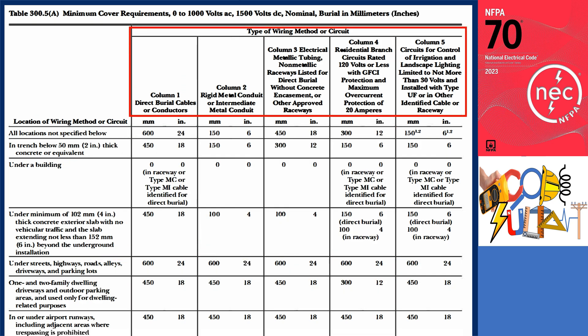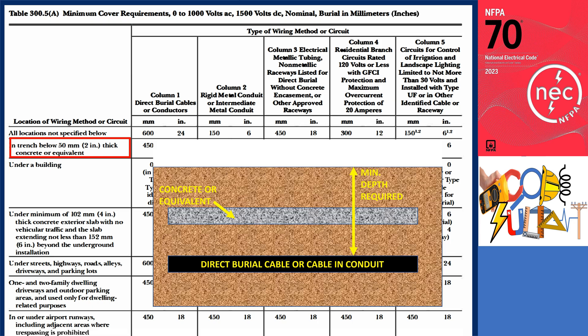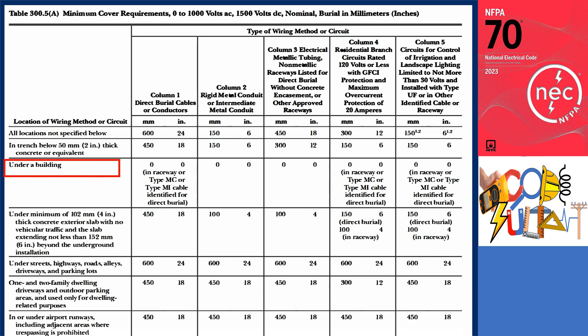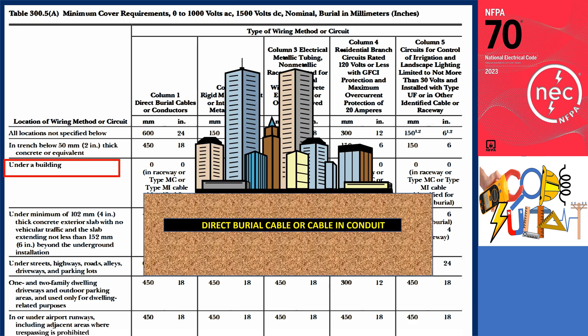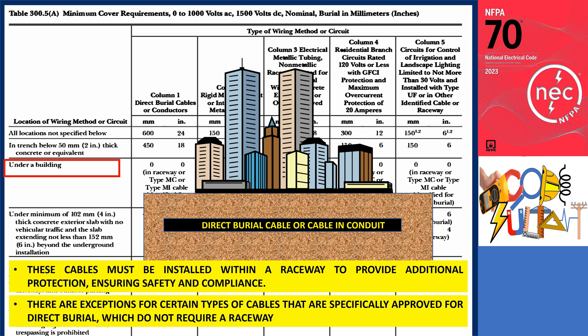These five different wiring methods or circuits can be used in various locations. The first location type applies to any locations not specified below. The second type is for areas where the wiring is buried under concrete or an equivalent material less than 50 millimeters thick. The third type covers any direct burial cable run under a building — these cables must be installed within a raceway to provide additional protection, though exceptions exist for certain cables specifically approved for direct burial.